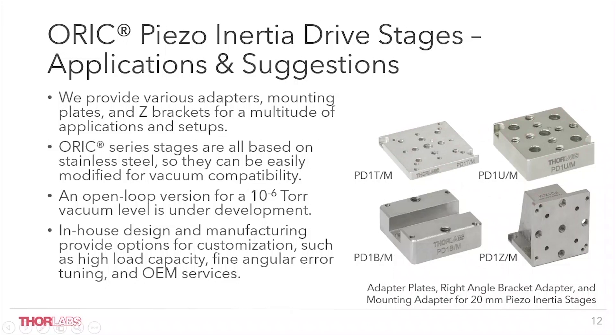As well as M4 tapped holes. The mounting plate provides a fine mounting surface with flatness error less than 5 microns. We recommend using it to avoid warping of the stage and to obtain expected performance.